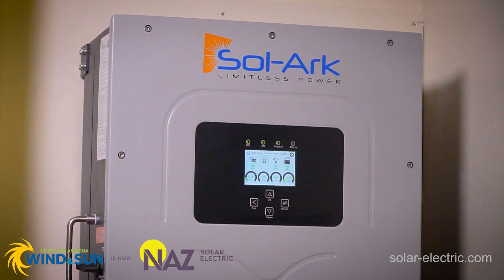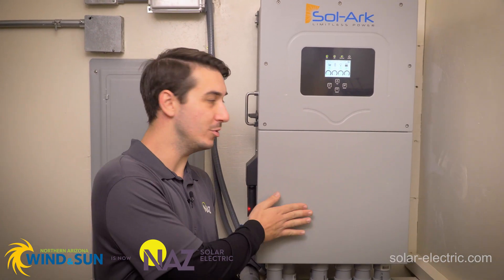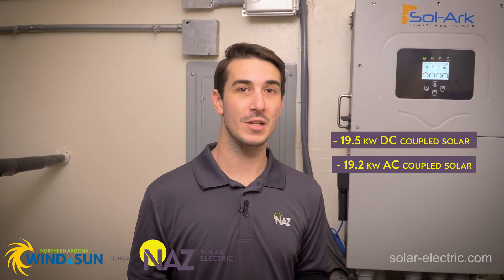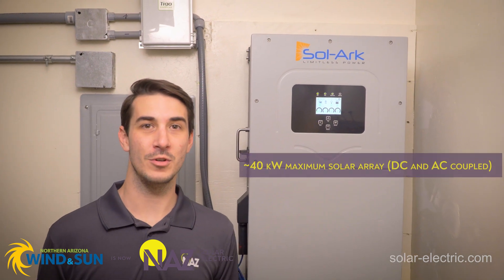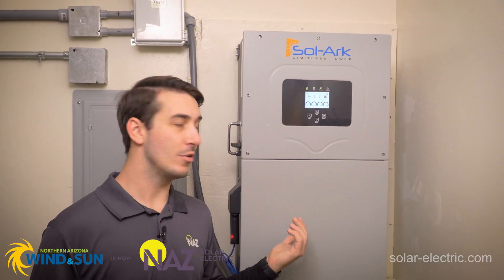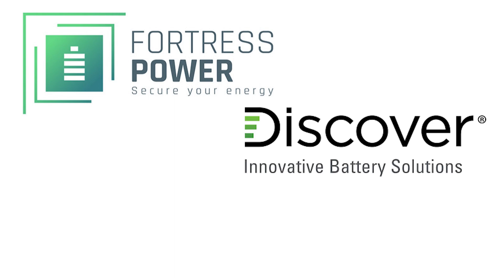The Sol-Ark 15k, just like all of their other models, is a hybrid all-in-one inverter system. Virtually everything you need for a complete system is built right into the inverter. It's a 120/240 split-phase output with a 48-volt nominal battery input. You can connect 19.5kW of DC-coupled solar plus an additional 19.2kW of AC-coupled solar, meaning you can load a single inverter with almost 40kW of solar. During a grid outage, the Sol-Ark 15k can provide up to 12kW — that's 50 amps — of usable power from the batteries to your loads. This inverter also has closed-loop capabilities with several lithium battery manufacturers like Fortress, Discover, and SimpliPhi, to name a few.